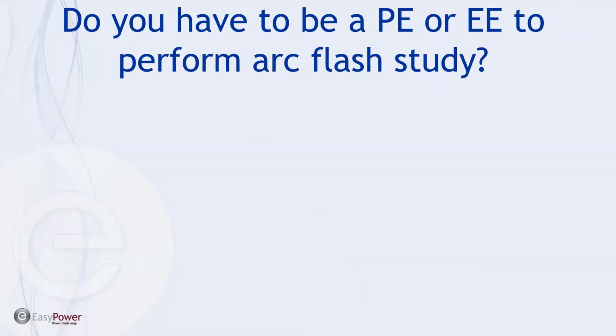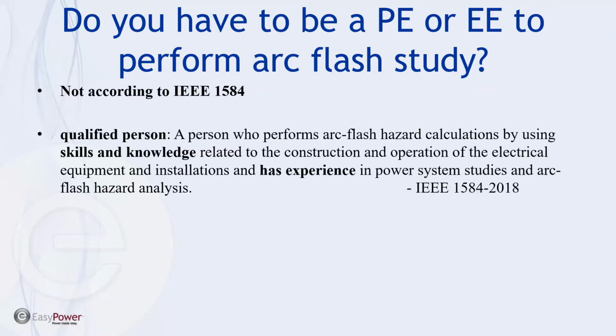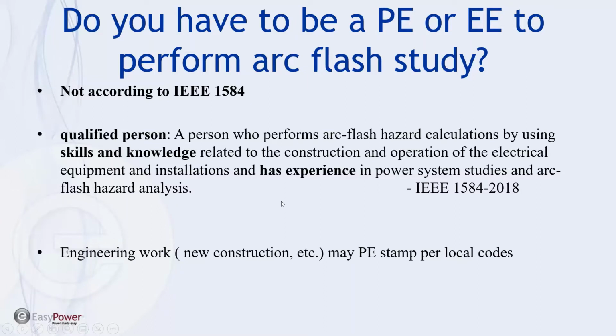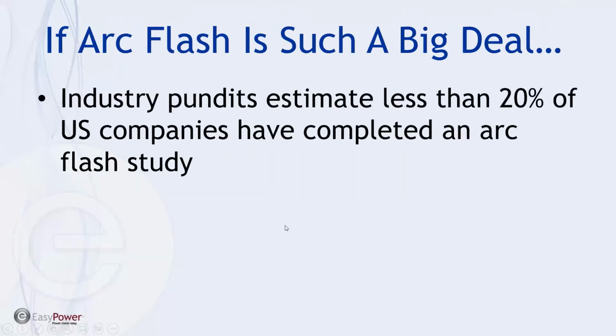Here's another question that comes up. Do you have to be a PE or an EE to perform an arc flash study? Well, not according to IEEE 1584. It defines a qualified person as one who can perform arc flash hazard calculations by using skill, knowledge, and experience in power system studies. Now, when the arc flash study is part of new engineering work, there may be local codes that require a PE stamp, so you need to be aware of that.